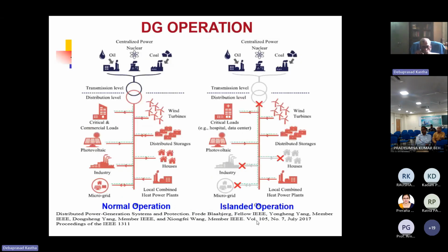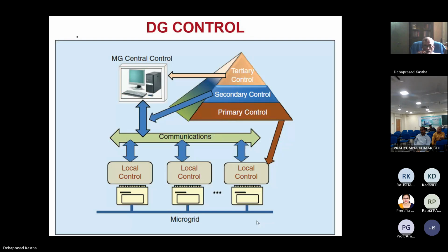And this is what I was saying. Normally, DGs will also operate with the connection with the grid, but if there is a fault in the grid, the DG may isolate itself so that the grid fault does not affect it and continue serving the local loads. So how do you control this? This is one idea of control.